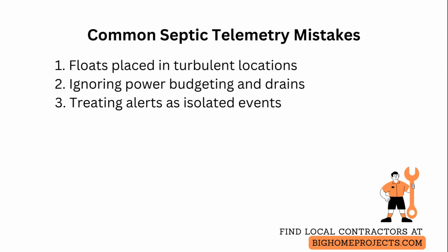A third frequent problem is treating alerts as one-off events instead of patterns. Respond to repeated minor alerts by reviewing the trend log for gradual changes in cycle length or level that precede a failure, and schedule preventive maintenance before the system trips.